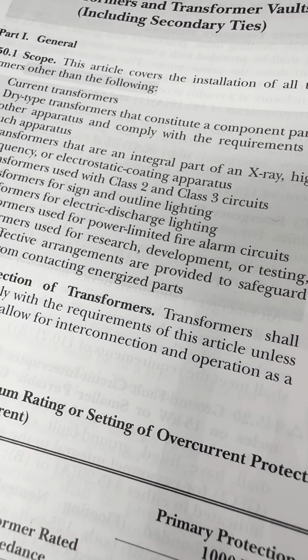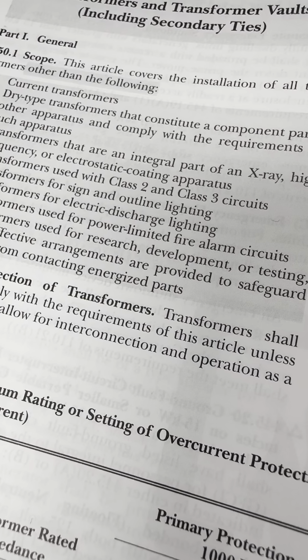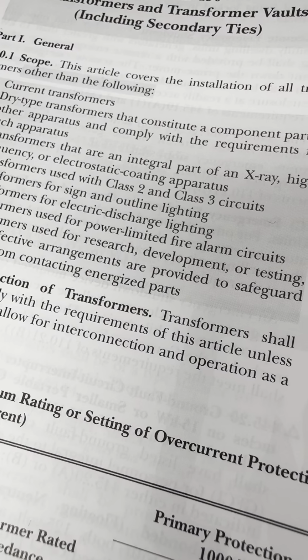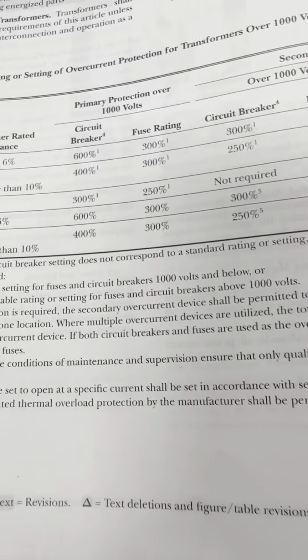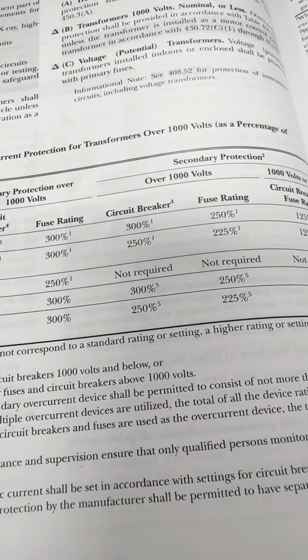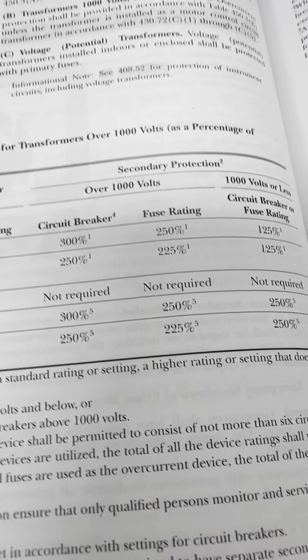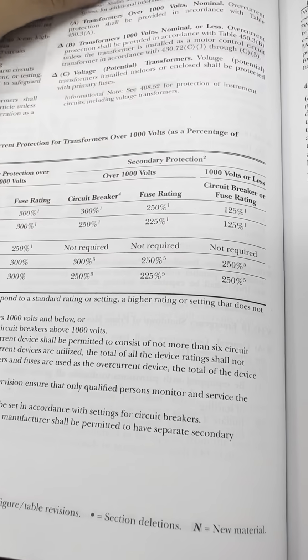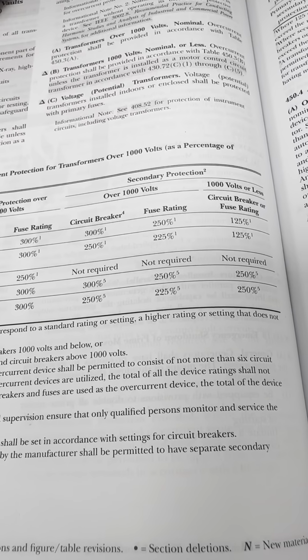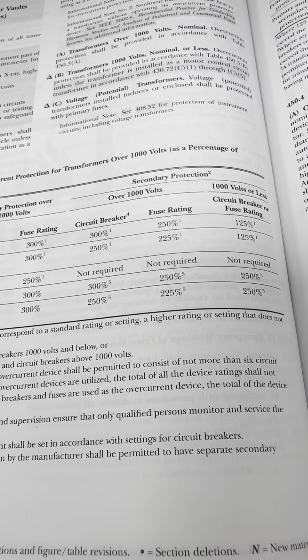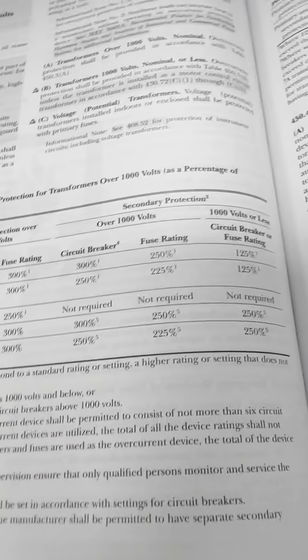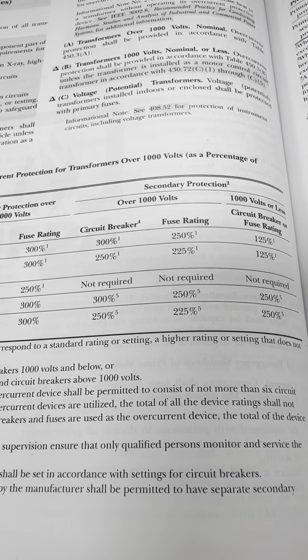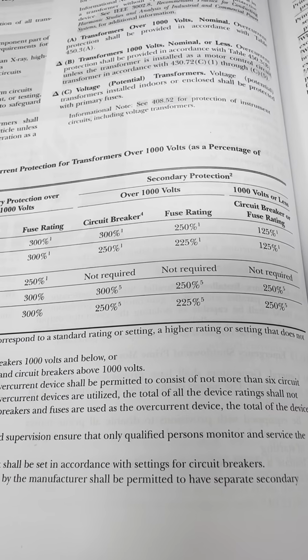All right, our next set of columns is for our secondary protection. Well, the first sub-columns that it breaks down into is over 1,000 volts or less than 1,000 volts. So again, we have 480 on our side, so we are 1,000 volts or less. And if we look there, at that point, it does not matter if you have a circuit breaker or fuse because they're all listed in that same column there. But looking at that very last column, what percentage do y'all see for the secondary? 250. So that's just kind of our notes over this transformer protection here.